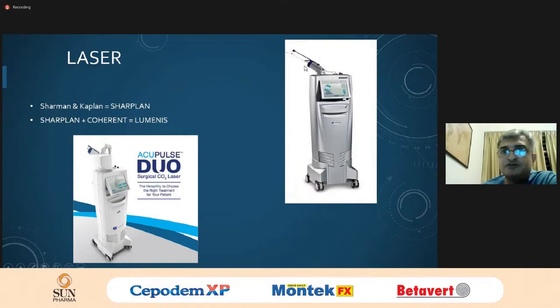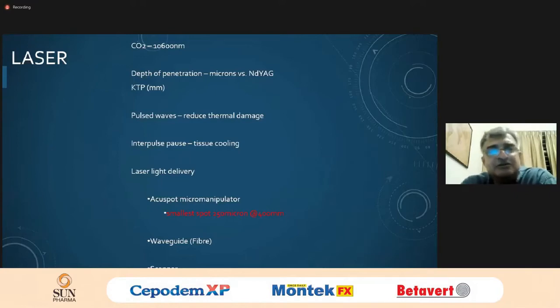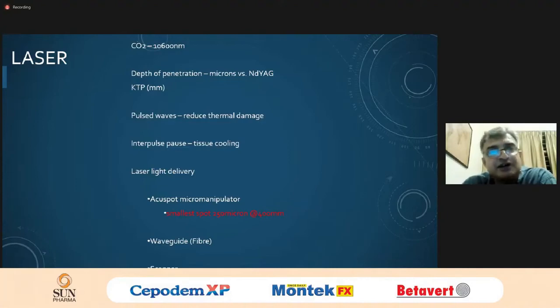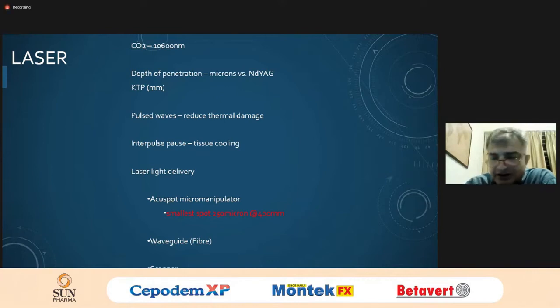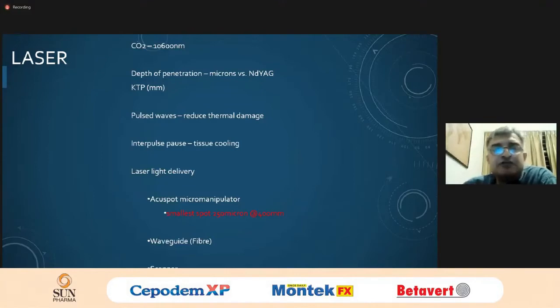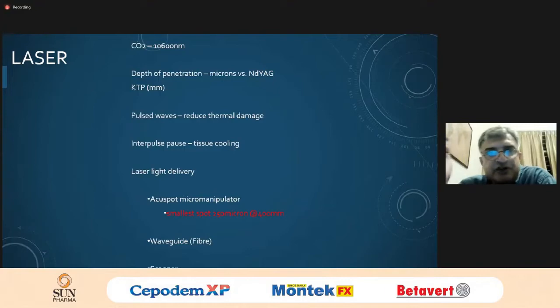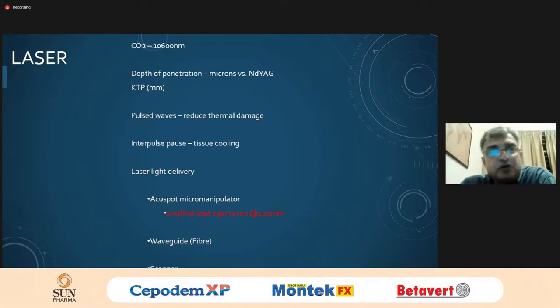The carbon dioxide laser has an intrinsically long wavelength. One problem is that many fibres designed for much shorter wavelength systems — the KTP, the holmium-YAG — simply cannot handle the CO2 laser; the fibre would burn or blow up. So the original CO2 laser was a line-of-sight, straight-shot laser. That changed in the 1990s with the development of the OmniGuide and waveguide fibre, allowing this laser to be used in much more versatile settings.